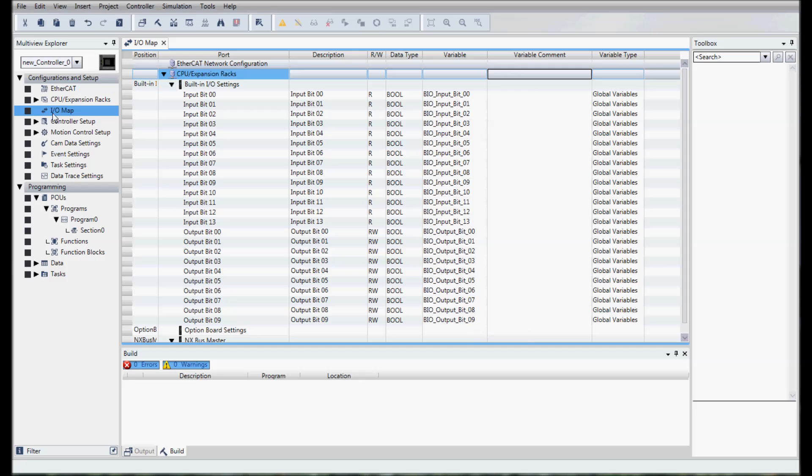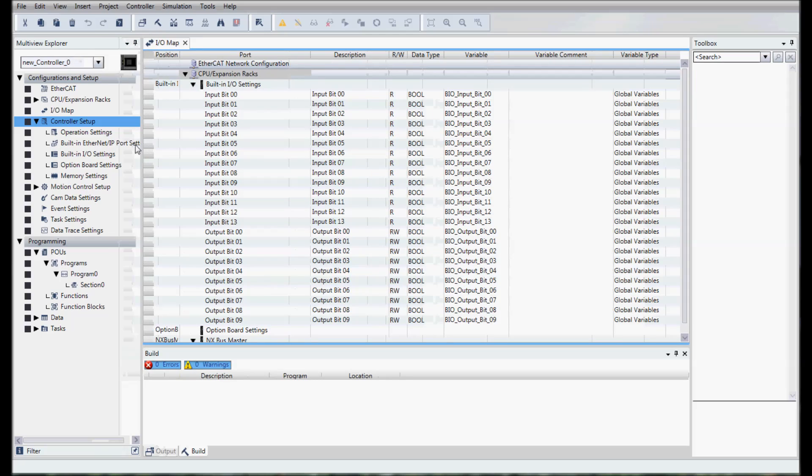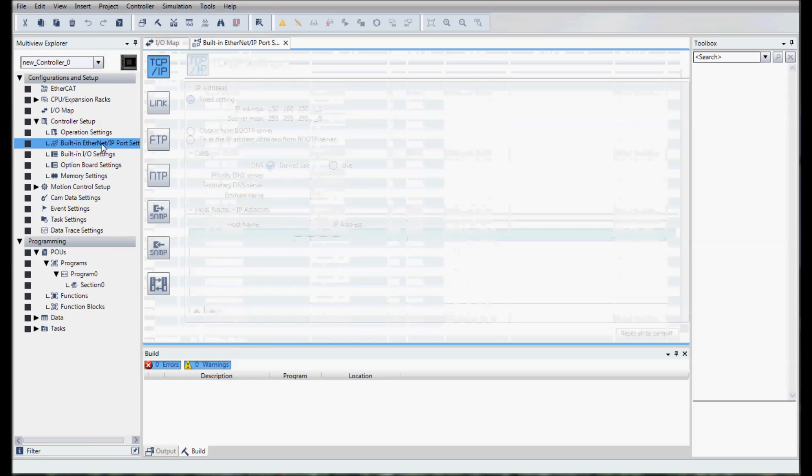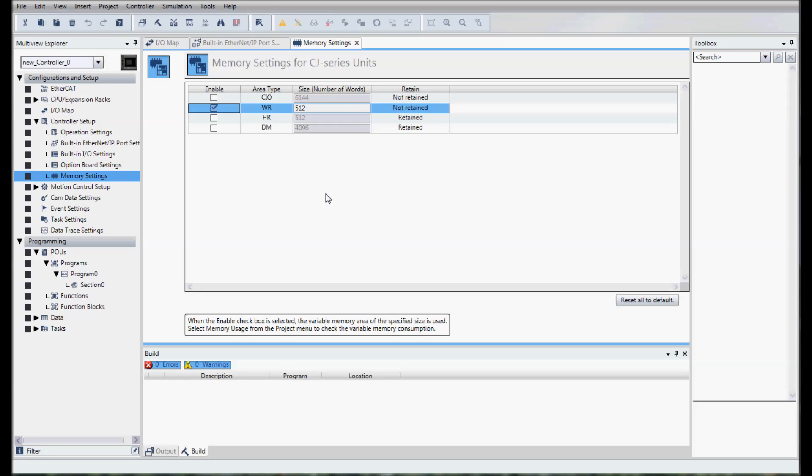The next thing we're going to do is go to our controller and look to see what the IP address of our PLC is. The IP address of our PLC is 192.168.250.1. Then we will go to memory settings and here we're going to use the W settings, the work relays, as our data that we're going to transfer back and forth between our NB HMI.